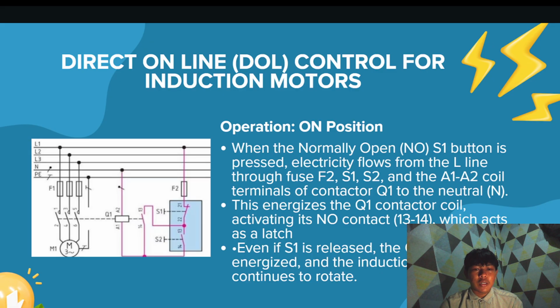Operation in the on position. When the normally open S1 button is pressed, electricity flows from the L line through fuse F2, S1, S2, and the A1, A2 coil terminals of contactor Q1 to the neutral. This energizes the Q1 contactor coil, activating its normally open contact, which acts as a latch. Even if S1 is released, the Q1 coil remains energized and the induction motor continues to rotate.